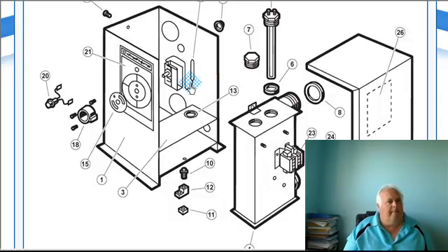So this is one big safety loop, okay? I think voltage hits this T-stat first, then goes to your heater light. The light could be on, but nobody's home because if it's not getting the proper pressure with the flow, detecting flow, you could have a bad pressure switch too. I'm not saying you can't. But if it's not detecting flow, it's not going to read.